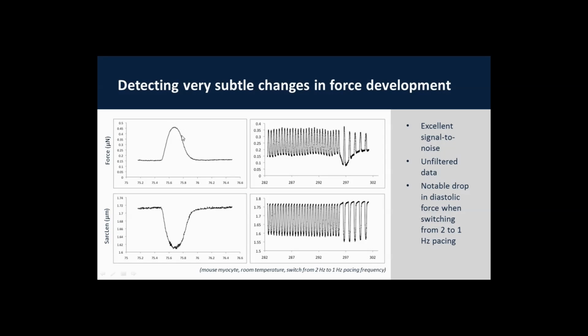This shows you another tracing. Here we see the nice signal-to-noise ratio. It allows you to measure very subtle changes. So this is a mouse myocyte placed at room temperature, here at 2 Hertz. Even at 2 Hertz, they already become somewhat calcium overloaded at room temperature. And you see as soon as you switch down the pacing frequency, there's extra time for reuptake of the calcium, so the diastolic force drops dramatically. You get a really strong contraction, and then within 3-4 beats, there's a new equilibrium.